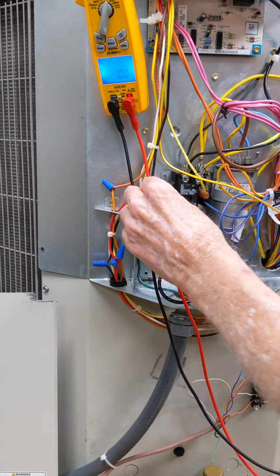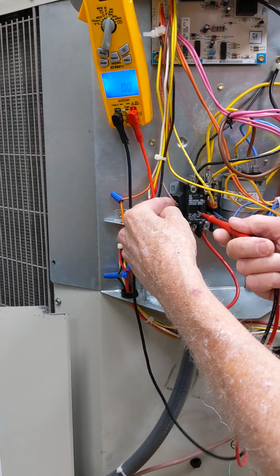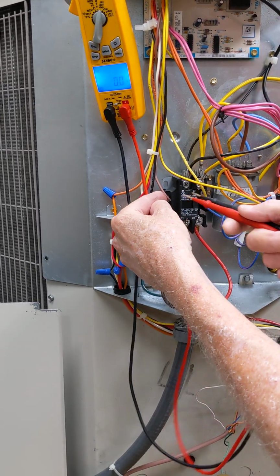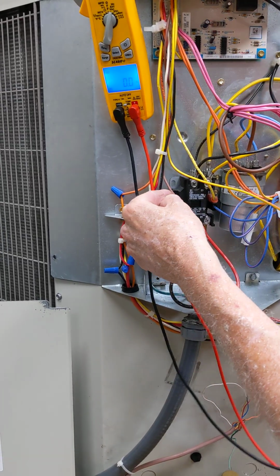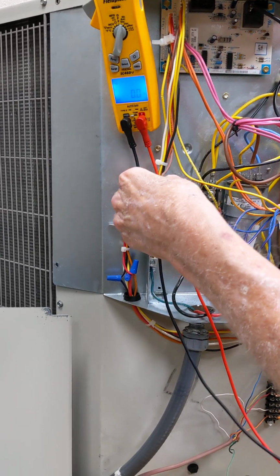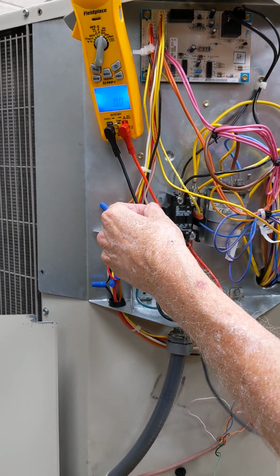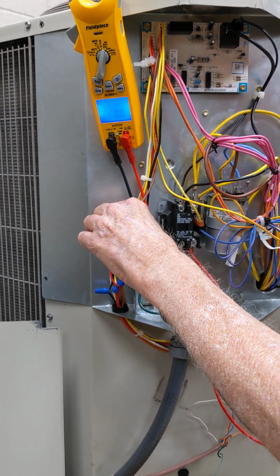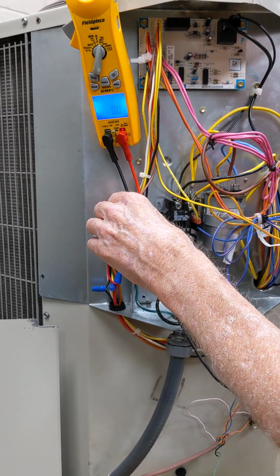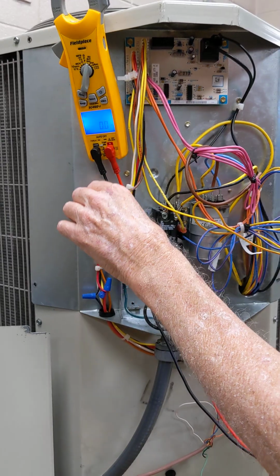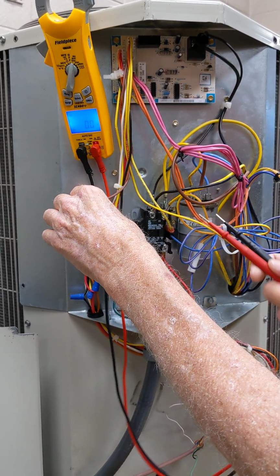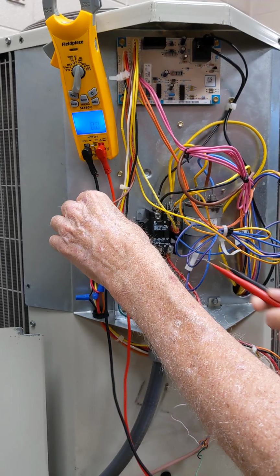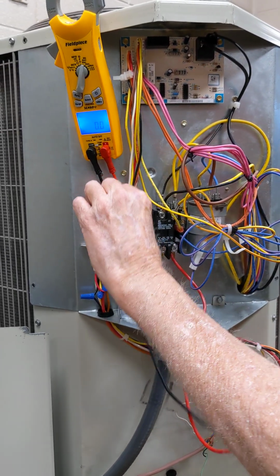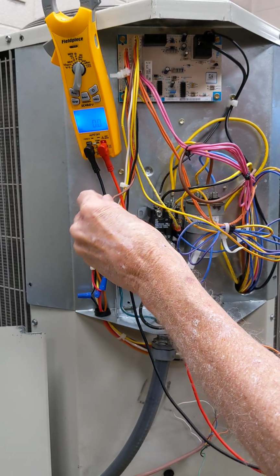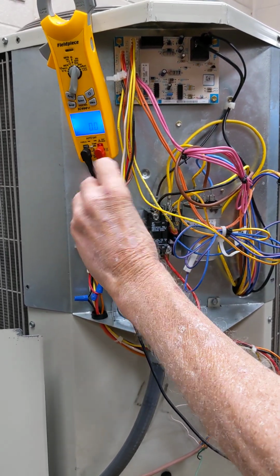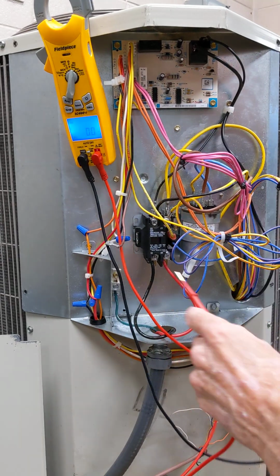And for you more advanced people, I can come here. Now, I don't have a call because that's not pulled in. But this is the common. If I chase it up, it's going to say common up here. So this is the common. If I pull the common and I still have electricity coming from the air handler, if I accidentally touch this on something, as long as the stuff is grounded, you know, the transformer's grounded, I don't have a problem. If I pull one of these hot wires or signal wires and it accidentally touches something, I'm in big trouble, okay? I just blew a fuse over there, at least a fuse, maybe the thermostat, maybe the fuse, the thermostat, and the transformer. We don't know. It could be all kinds of stuff. A circuit board over there, circuit board over here.